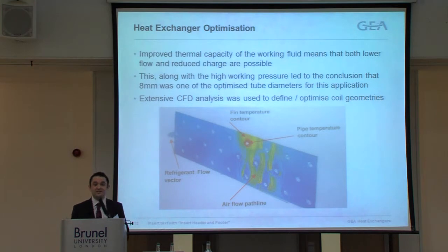Okay, in addition to the testing, we were able to complete some CFD analysis with the university's help. Now, at GEA, CFD is sometimes referred to as colourful for directors. In this case, it wasn't. We were getting as much out of CFD as we possibly could. So as you can see, the temperature distribution or the air distribution across the coil block was enabling us to optimise the tube geometry within the coil, ensure we're using as much surface as possible, and ultimately allow us to optimise our coil design.